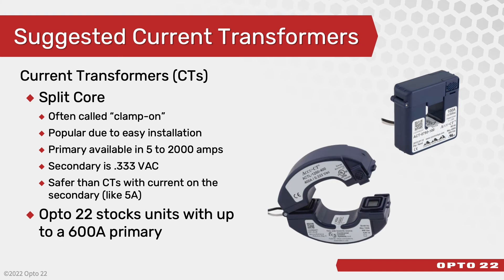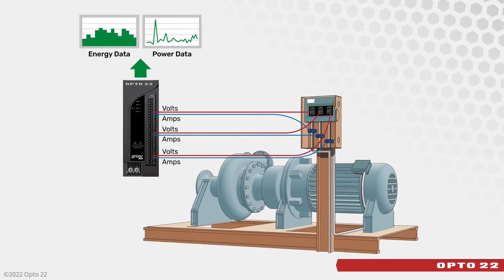Split-core CTs are typically available up to 2000 amps on the primary; Opto 22 stocks up to 600-amp units. The secondary output signal of these units is at 0.333 VAC, though some CTs have a 5-amp current secondary. In a typical installation, the RIO EMU connects to a three-phase load such as a pump and motor. You bring back the voltage tap and the CT outputs directly into the RIO EMU, and with very simple configuration, energy and power data is available.